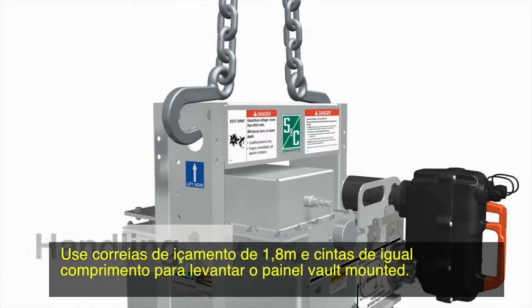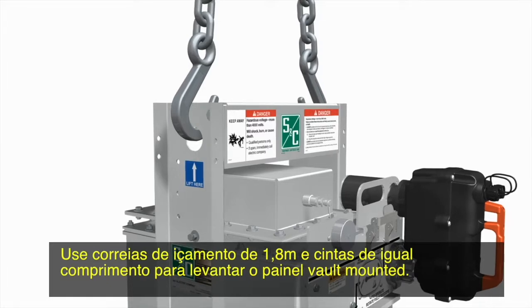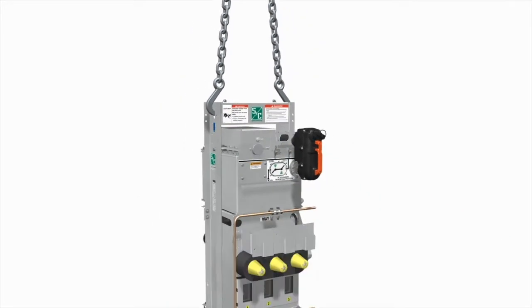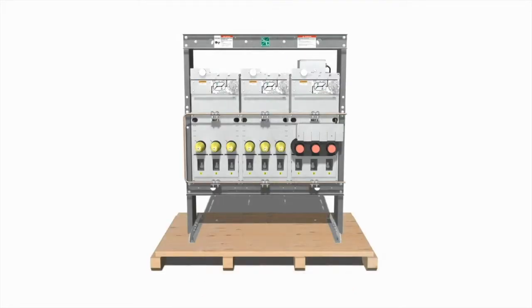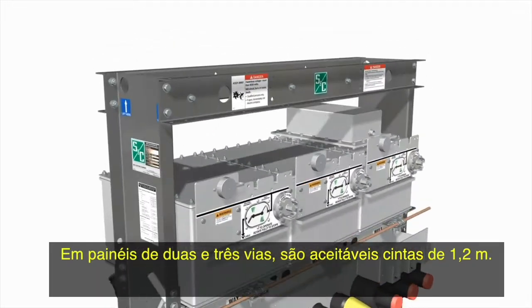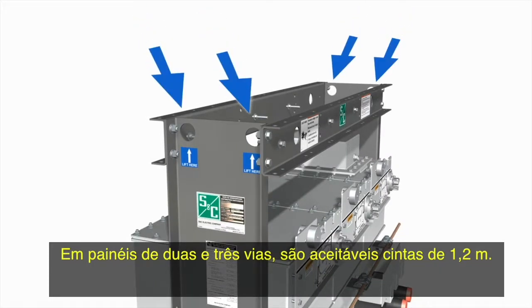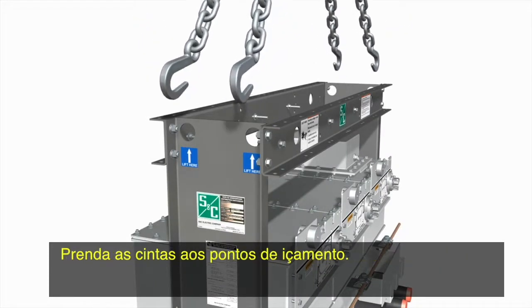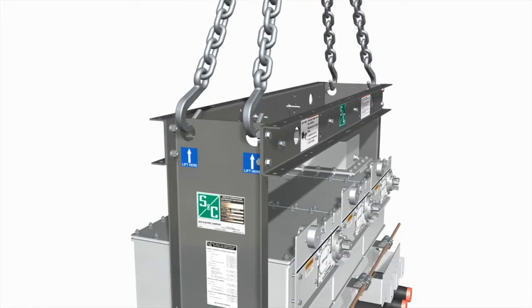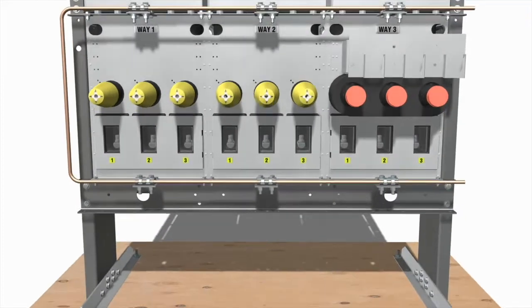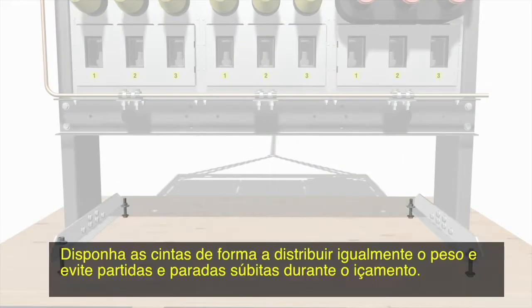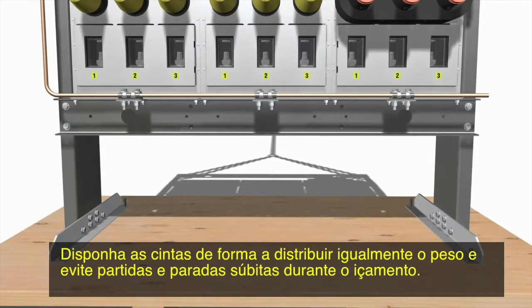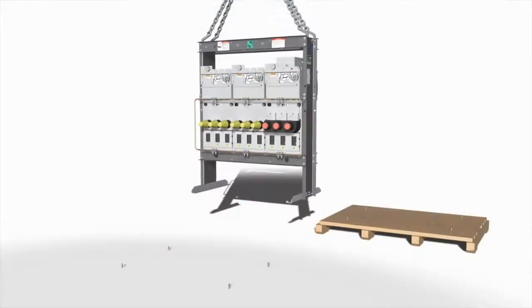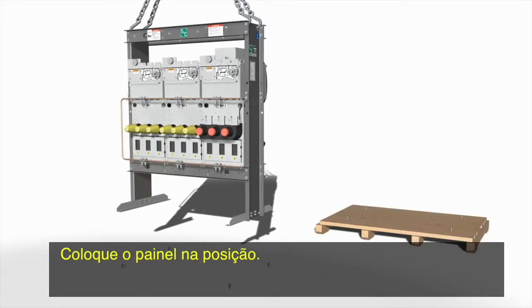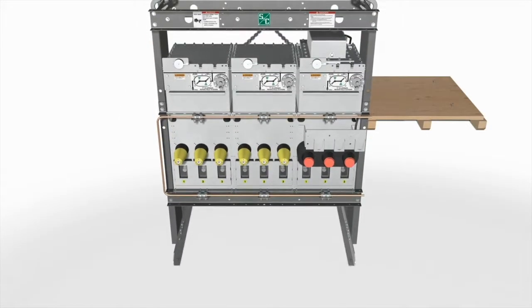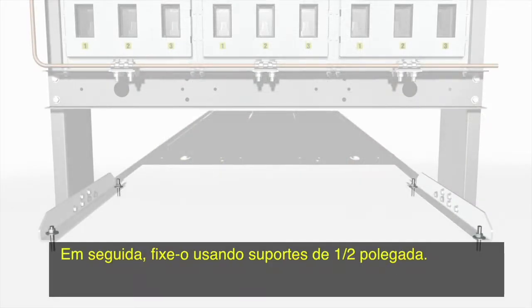Use 6-foot or 183 centimeter lifting slings of equal length to lift the vault-mounted switchgear. For two-way and three-way switchgear, lifting slings of 4 feet or 122 centimeters are acceptable. Attach the lifting slings to the lifting points. Arrange the slings to distribute weight evenly and avoid sudden starts and stops when lifting. Lower the switchgear into place. Then, secure the switchgear using half-inch fasteners.